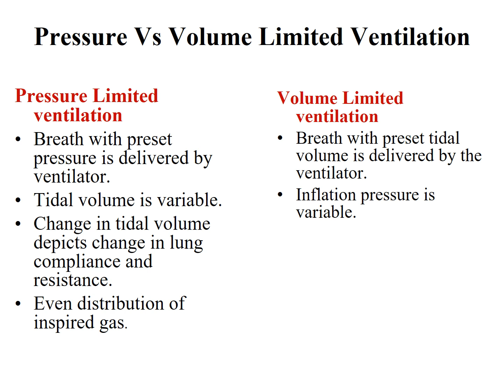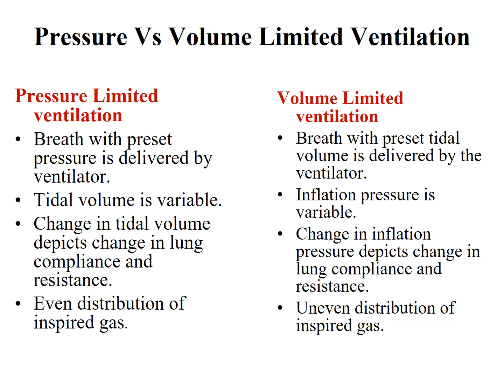So one breath after every 3 seconds, a cycle of 3 seconds, time trigger every 3 seconds, and it is limited by a tidal volume of say 80 ml. So the ventilator will continue giving the inflation pressure till this tidal volume is achieved. So here the inspiratory pressure would vary. And again, if you say you want to give 10 ml per kg, depending upon the lung compliance and the resistance of the airways, the pressure would actually vary. However, in this sort of ventilation, there would be uneven distribution of inspired gases. This is one of the reasons, among others, why we generally tend to prefer pressure ventilation, not mandatory, but preferably we go for pressure ventilation because of this and many other reasons.